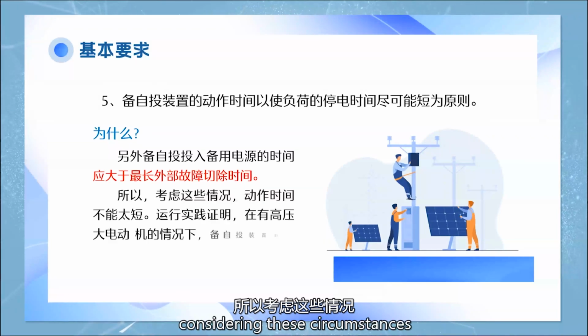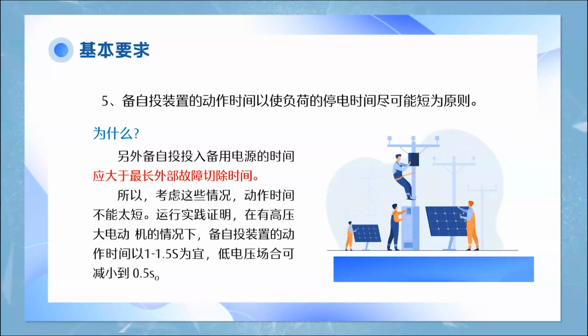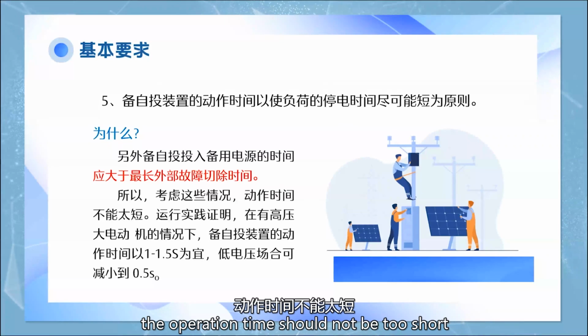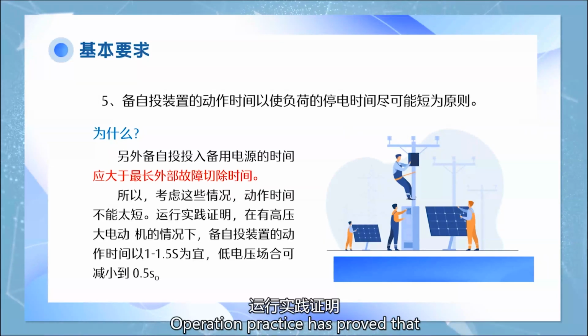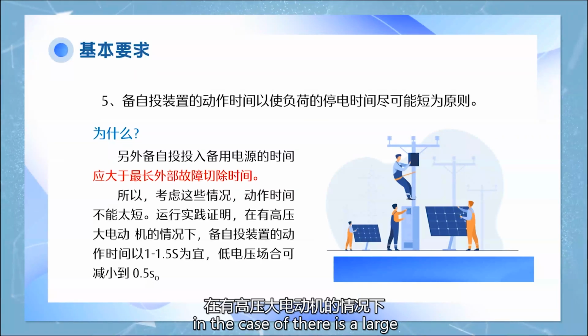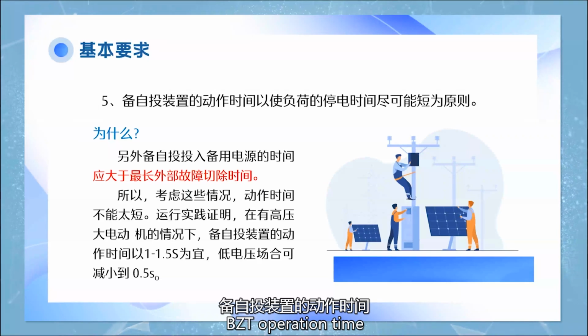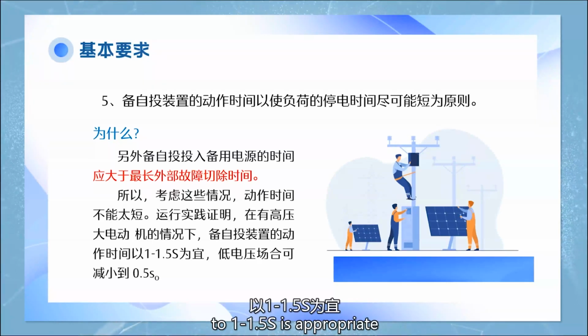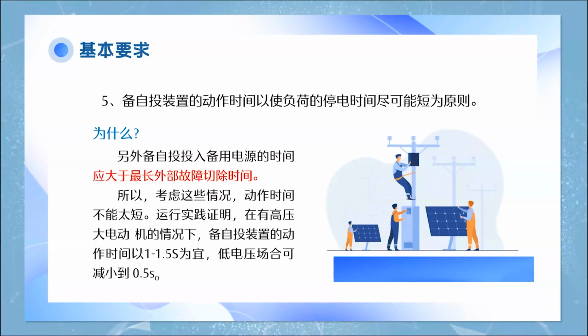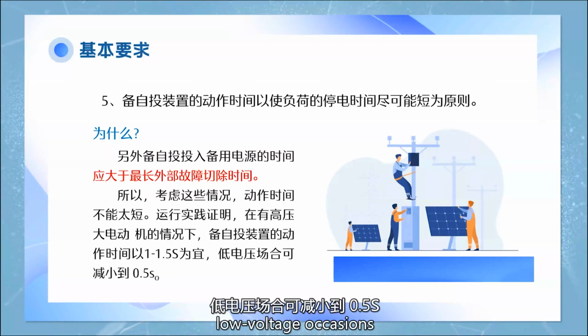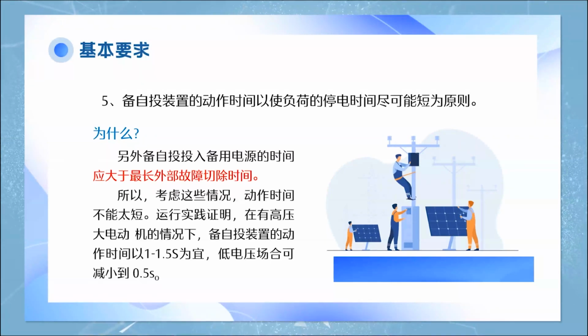Therefore, considering these circumstances, the operation time should not be too short. Operation practice has proved that in the case of a large high-voltage motor, a BZT operation time of 1 to 1.5 seconds is appropriate. Low-voltage occasions can be reduced to 0.5 seconds.